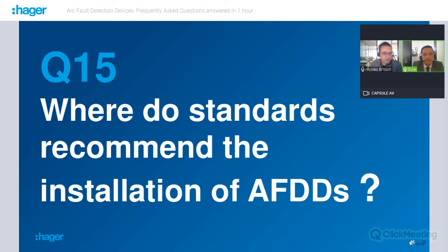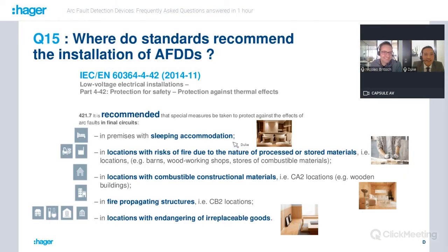Okay, but where do the standards recommend the installation of AFDDs exactly? Do you know the chapter? Okay, I will open my book, my Bible, and see the chapter. 421.7 clearly recommends special measures to be taken against the effect of arcing in final circuits. So if you are in a final circuit and you are in a location with sleeping accommodations, a location with risk of fire due to the nature of processed or stored materials, for example woodworking shops, or a location with combustible constructional materials, for example wooden buildings, in fire propagating structures, for example high-rise buildings, in locations with endangering of irreplaceable goods, for example a museum or library, you can install AFDD to protect against electrical arcing and fire.